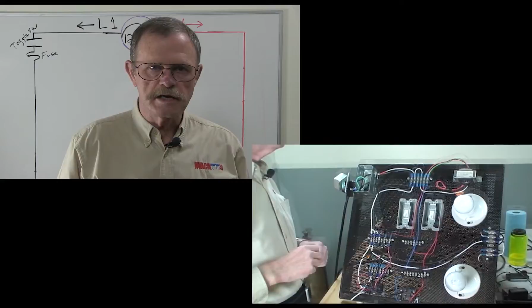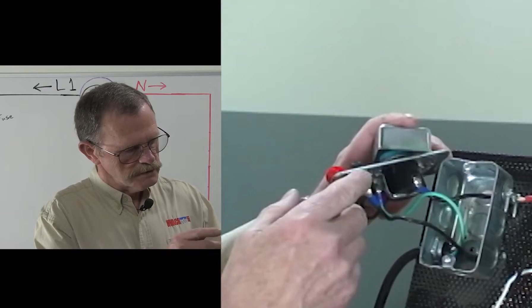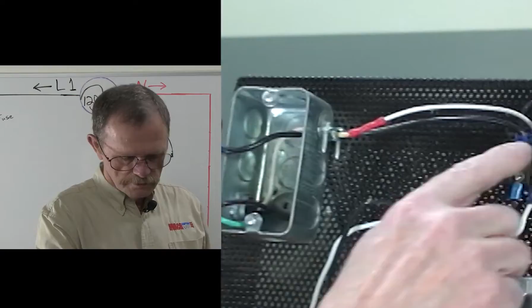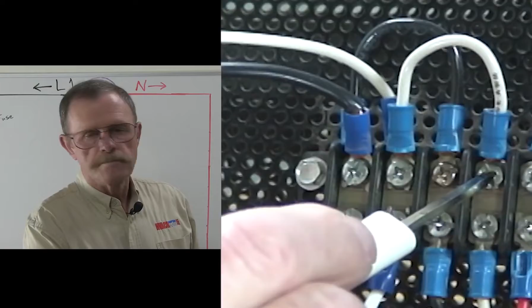I want to make sure you understand that a ladder schematic is electrically exactly correct to what's happening in the real wire. So I'm chasing the neutral. Neutral comes out of the power source, the extension cord, comes through the box. It doesn't go through any switches or anything else, and it comes over here to where it hits the terminal strip. I can see it parallels over here.